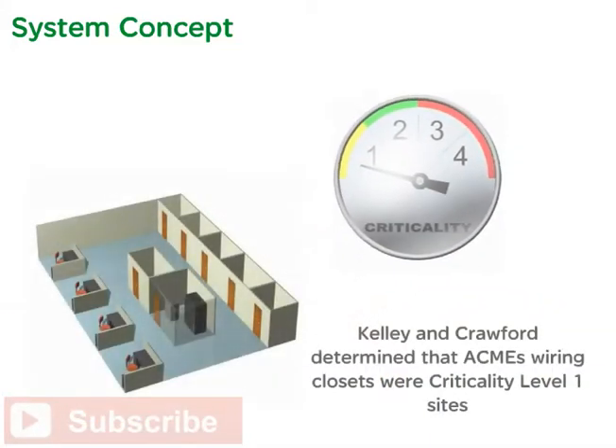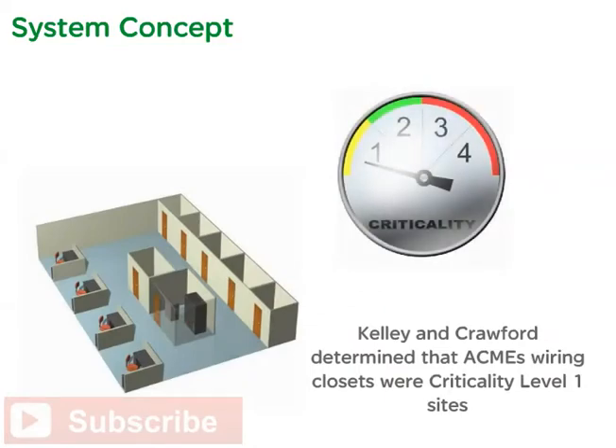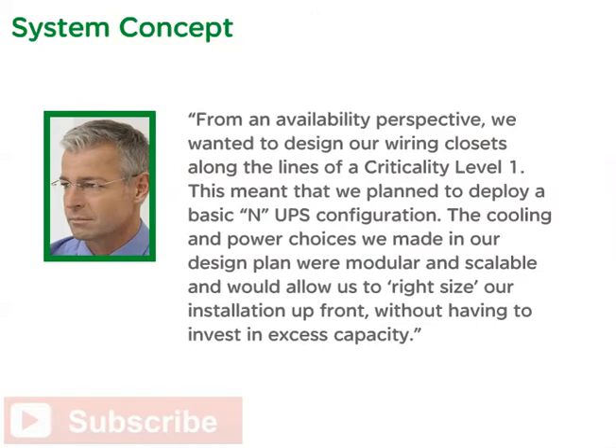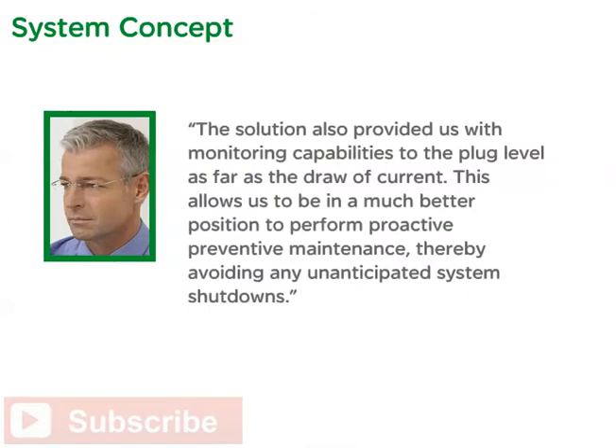Kelley and Crawford determined that Acme's wiring closets were criticality level one sites. From an availability perspective, they designed the wiring closets along the lines of criticality level one. This meant deploying a basic N-UPS configuration. The cooling and power choices made in the design plan were modular and scalable, allowing them to right-size the installation up front without investing in excess capacity. The solution also provided monitoring capabilities to the plug level, allowing proactive preventive maintenance and thereby avoiding unanticipated system shutdowns.